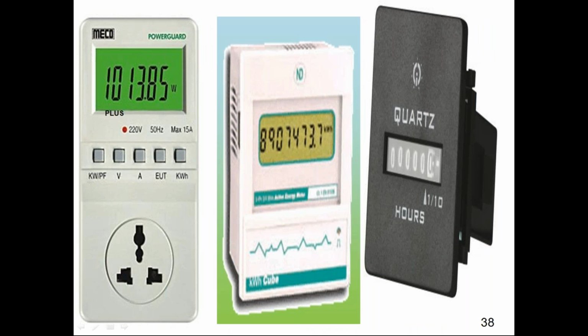This is to be installed in all the industries where they measure the run hour, how many hours the machine is running, and what is the kWh per machine it is taking up. And this is a measurable quantity. Ultimately, we know the units per hour. See, some of the machines can be running for 12 hours, some of the machines can be running for 18 hours. If a machine is fitted with a run hour meter, which costs only 400 rupees, and a kWh meter, you know what the units per hour for the given machine is, the loading for the given machine is known, and then we know whether the machine is loaded optimally. Next, please.